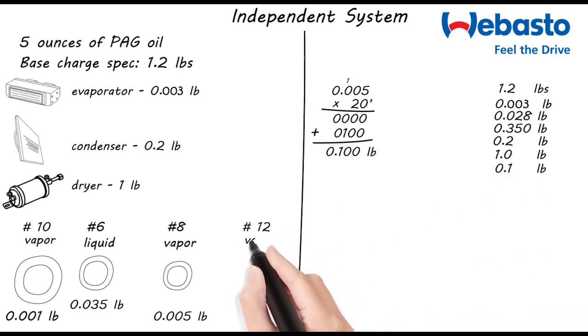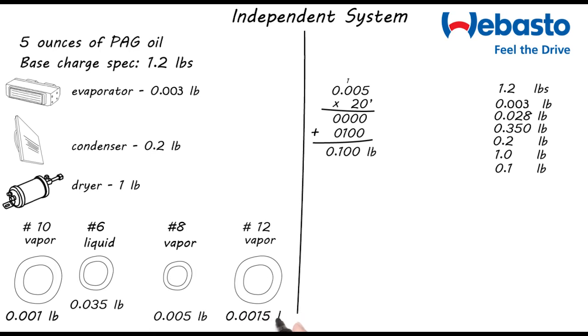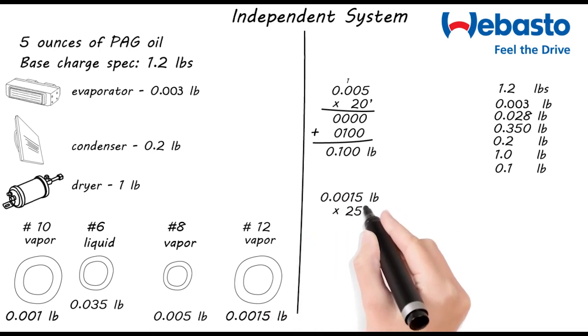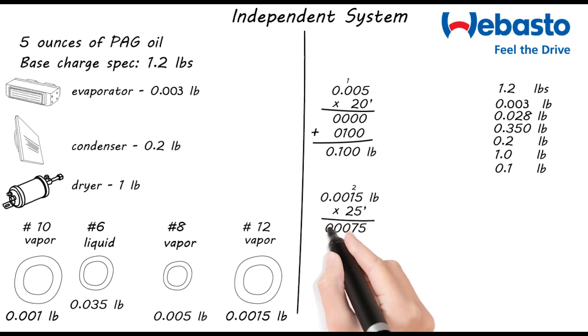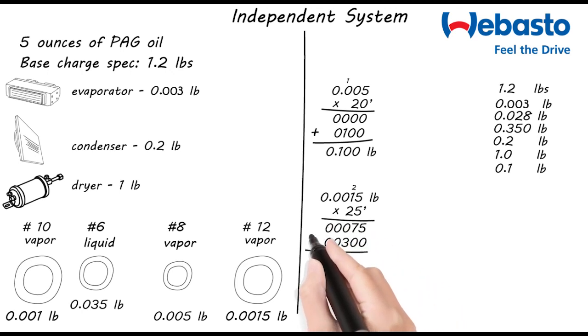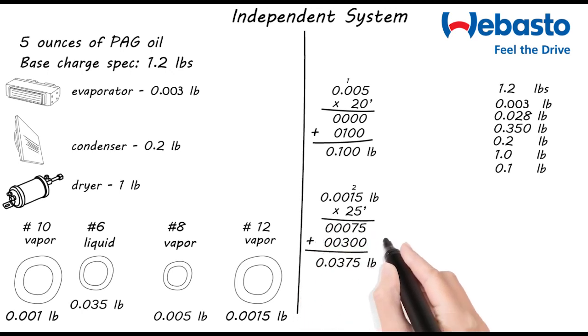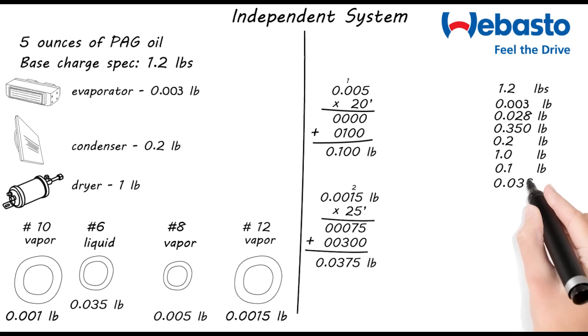We also have 25 feet of number 12 hose also on the vapor side of the system. We'll add 0.0015 pounds for each foot. That comes out to 0.0375 pounds. So we'll just round that up to 0.038.